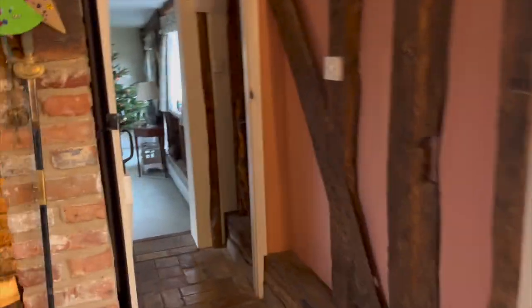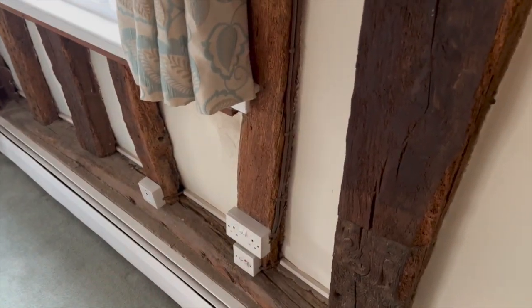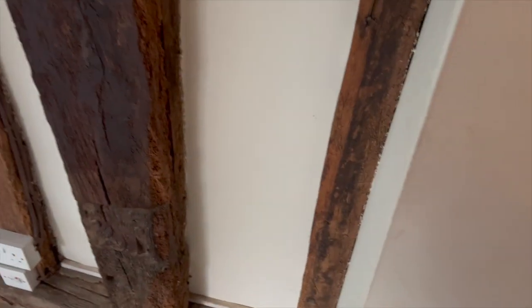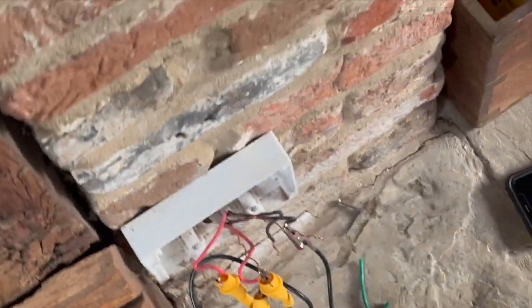This house is stunning. We're just doing a report on this - a lot of it's called clipped direct, but we've just found that it's got 1mm earth in there as well. It's got some interesting things, like those lights are actually spurred off the ring main, and they have actually been switched from here as well, so that's quite interesting. We'll look into that. We've got some 5 amp plugs to do, so Ebzee is just doing the end-to-end. We've discovered that this has got a 1mm earth - you can tell if it's got a 1mm earth, that just ages the cable really.